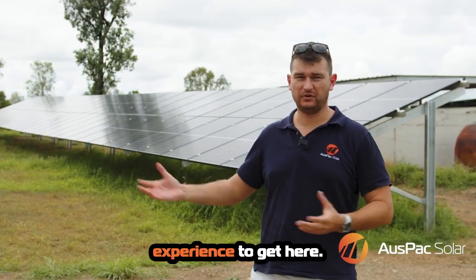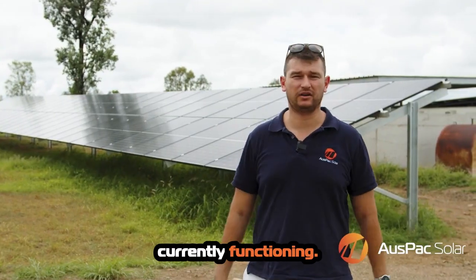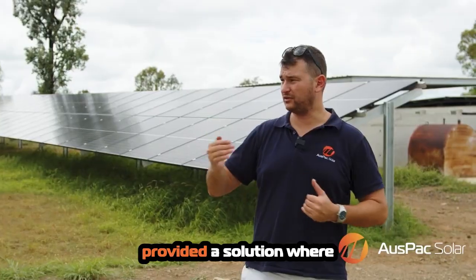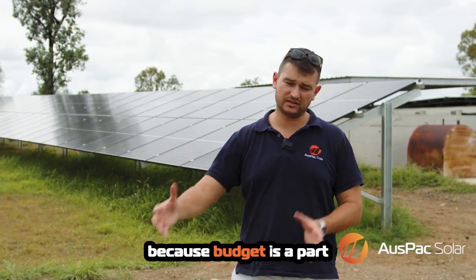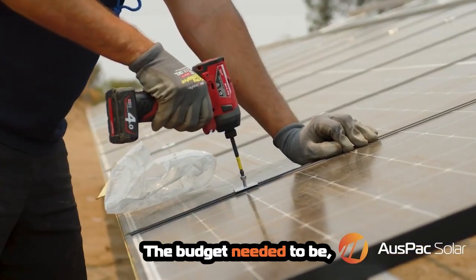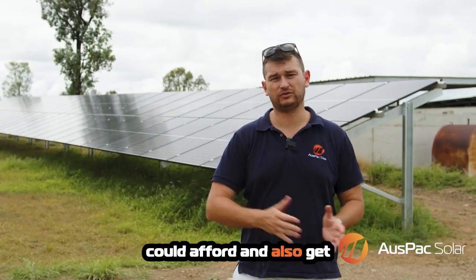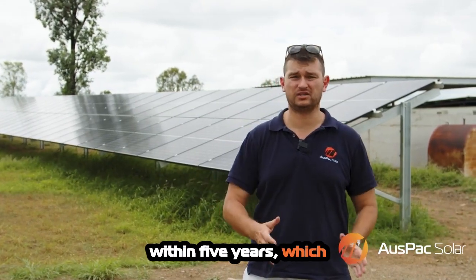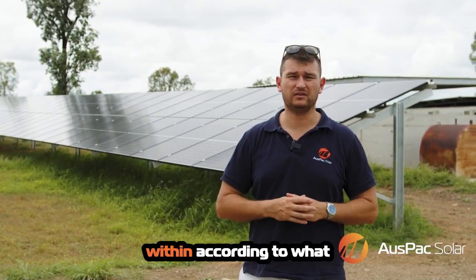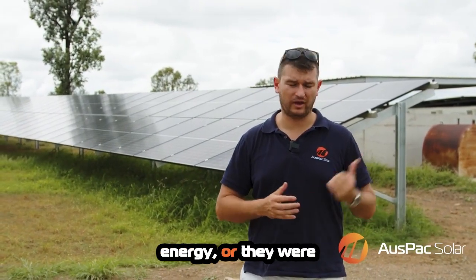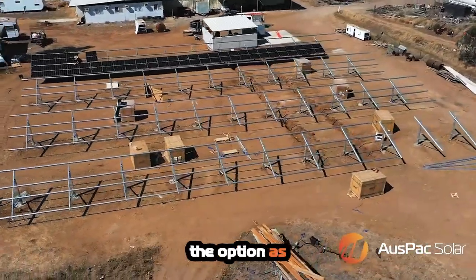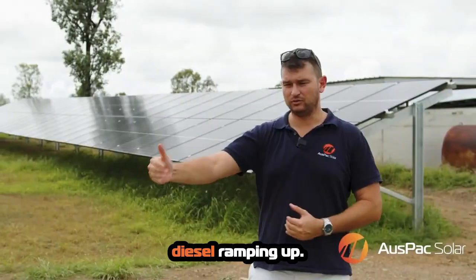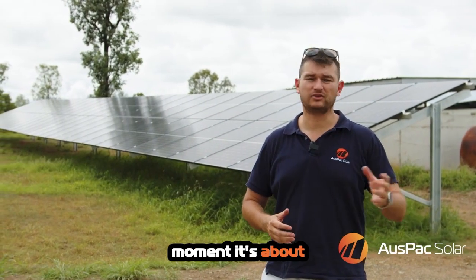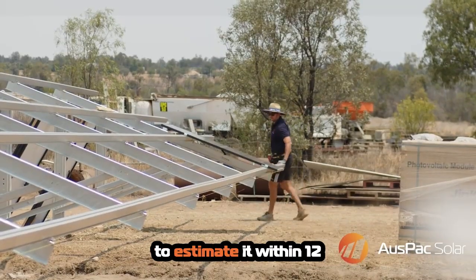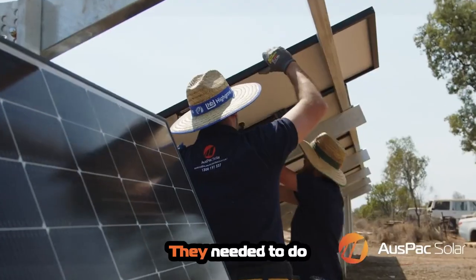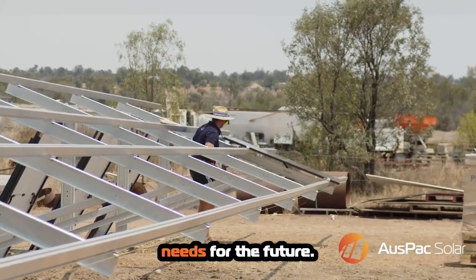Obviously it took a lot of knowledge and experience to get here, but we have got here and the system is currently functioning. What we did first is we provided a solution where we could financially, because budget is a part of the design requirements, the budget needed to be one which the customer could afford and also get a return on investment within 5 years, which with our projections we will well and truly be within, according to what they're spending on their energy, or they were on their diesel off grid. They didn't have the option to go on grid, and with the cost of diesel ramping up dramatically, at the moment it's about $2.20, $2.30. That's estimated within 12 months to be around $3. They needed to do something now to secure their energy needs for the future.